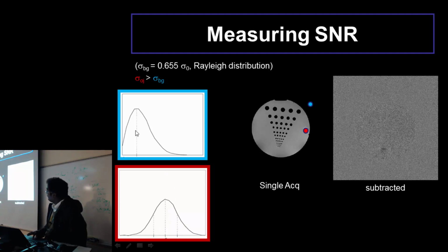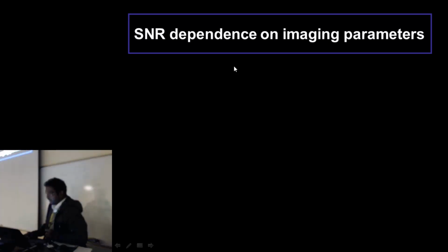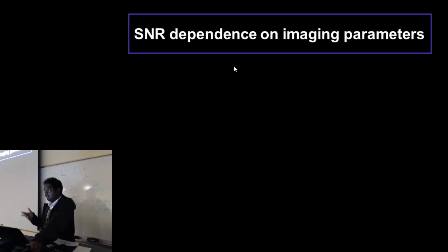So the standard deviation of this and this are related by the expression that you saw earlier, which is actually, that's here as well. So you can estimate for wherever you have non-parallel imaging, where the image is actually reconstructed through sum of squares, the noise behavior that we saw: the background is Rayleigh, and then the noise inside the object where you have signal is Gaussian distribution. That rule more or less is followed in an image where the image is reconstructed using sum of squares approach.